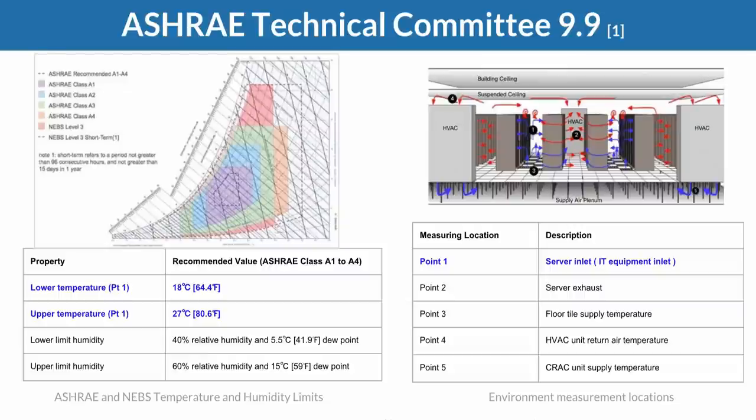In this case, we are looking at the performance of the temperature range at the inlet of an IT equipment, and we will be considering if the temperature of the air we're supplying to the device stays within a certain range. Different simulation types allow us to check and confirm that we are within the standard for other purposes or other properties of the flow. In this case, we're mostly focusing on the temperature part. Now, why is this important? Well, I would say, hey, I could push a lot of cold air, and be sure that I get the performance that I need and that the temperature is always below the desired 27 degrees and it's not too cold.